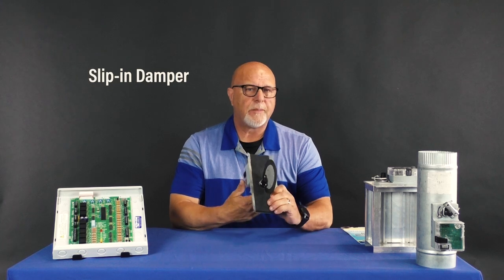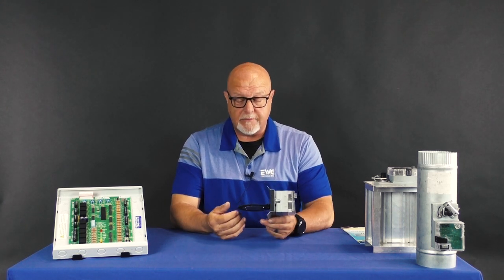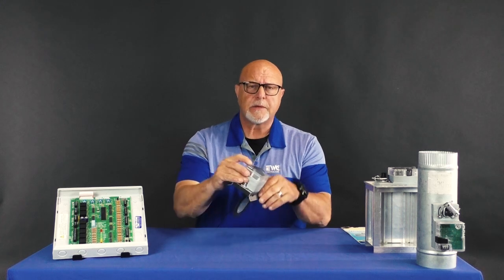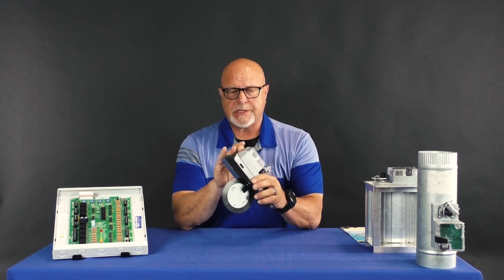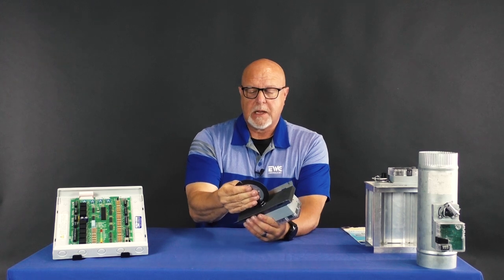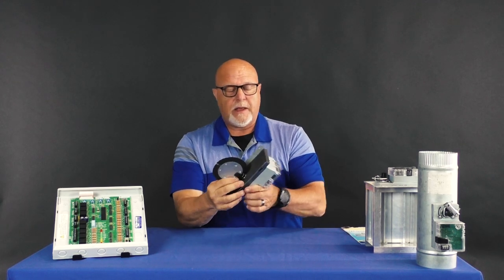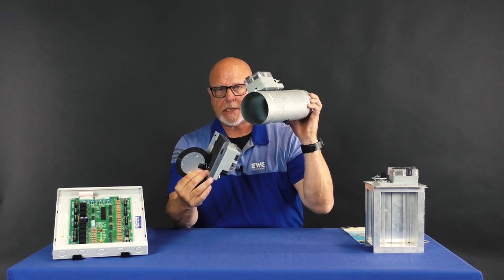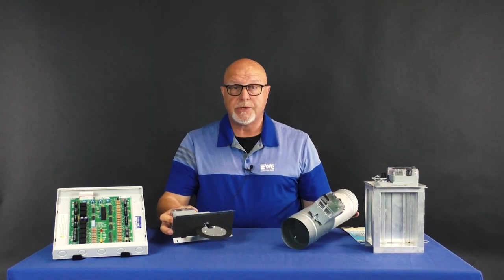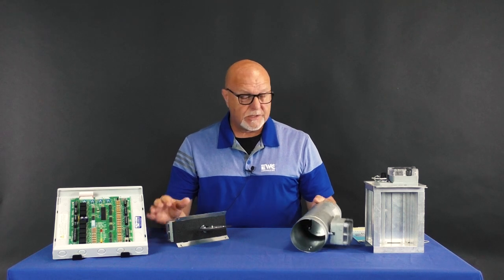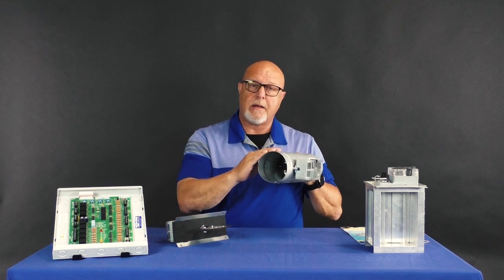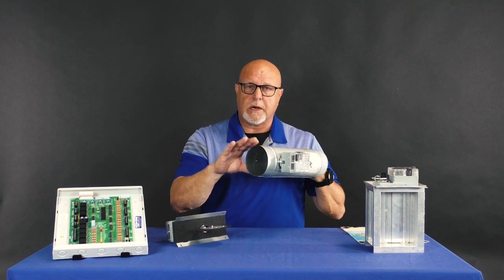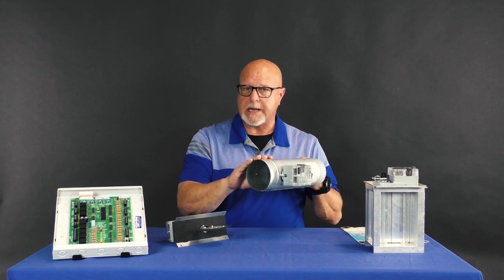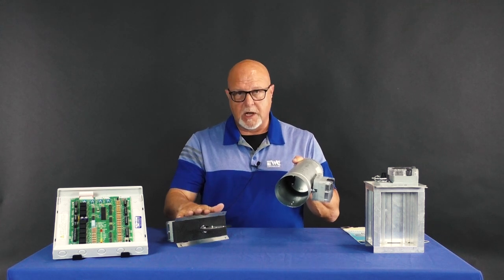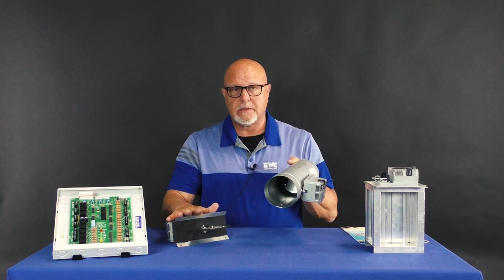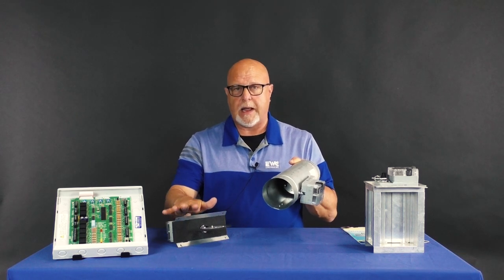This is our slip-in damper, or SID. This has truly innovated the retrofit industry. We make this 4 through 10 inch, and as you can see, it gives you a little bit better picture of the pour-on cellular foam gasket that we incorporated into the URD damper. This is very easy to install in a system. If you're looking at your supply plenum, your cold or heat runs would come off of that plenum. Right after that takeoff, you would cut a slot. This does come with a template for each size damper, and it will tell you exactly where to cut and how big to cut it.